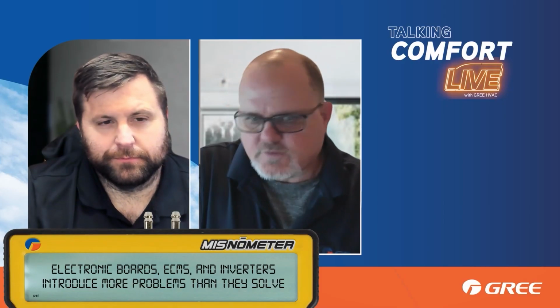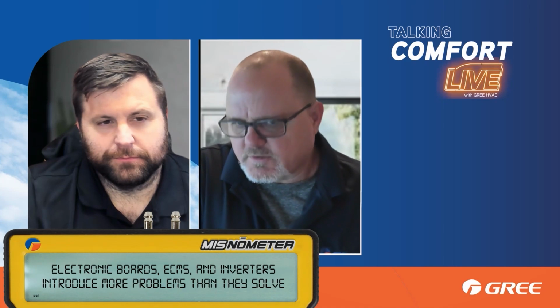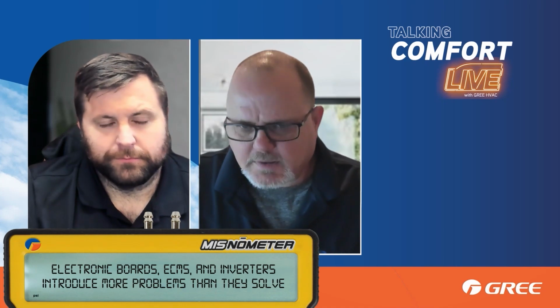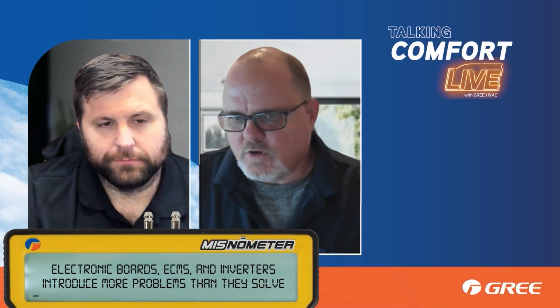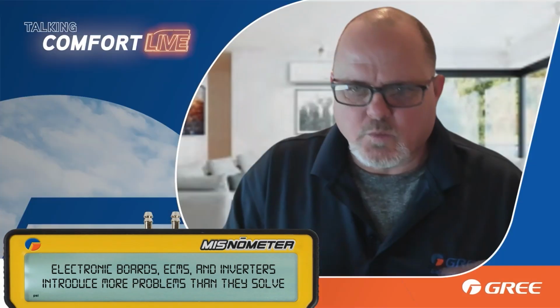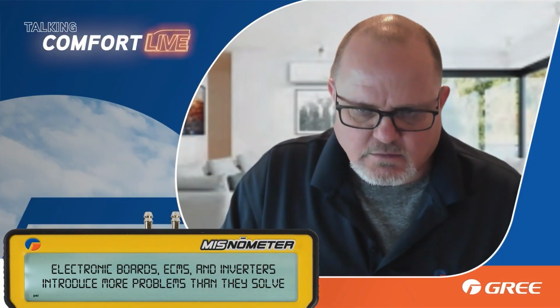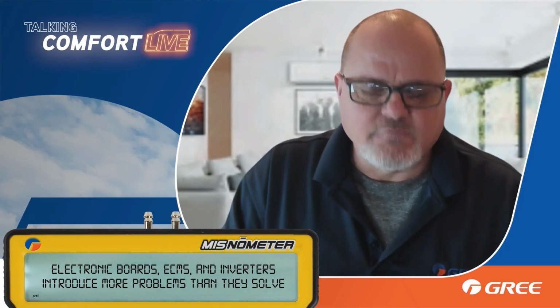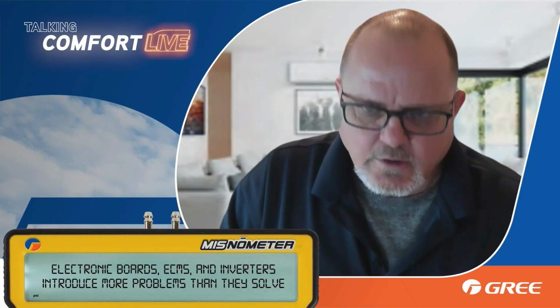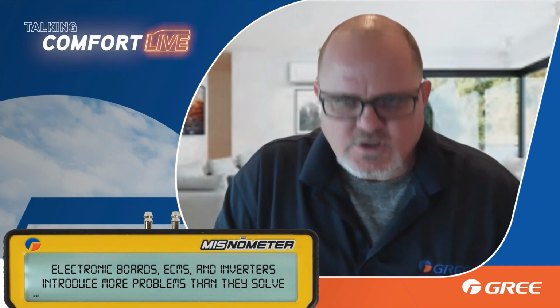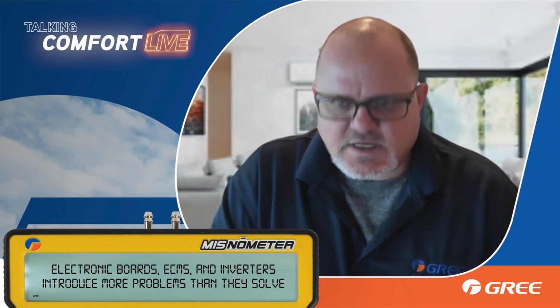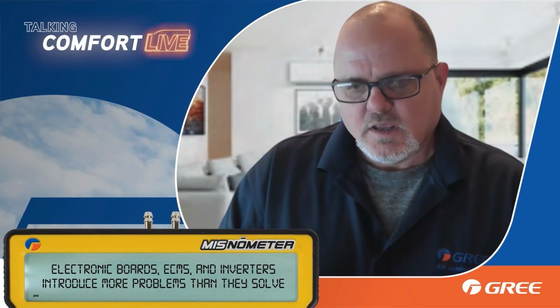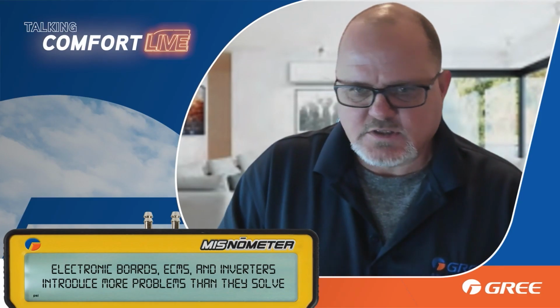Well, the bottom line is the whole machine was low on refrigerant because they had a refrigerant leak in the piping. But the machine wasn't out of refrigerant to the point where it wouldn't do anything. Right. Or actually throw it into an error code. Eventually, it's going to throw an error code. But during that run cycle, that's what I was getting at, is it'll slow itself down. It tries to save itself.